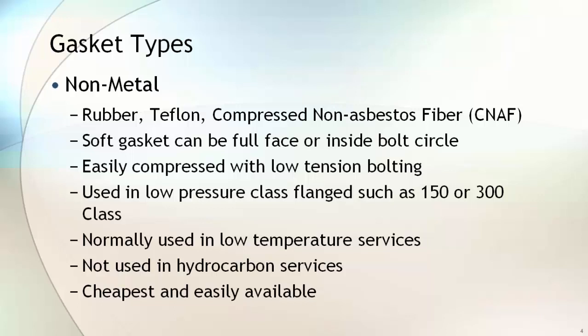Starting with non-metallic gaskets, the most common materials used are rubber, Teflon, PTFE, and compressed non-asbestos fibre. These are also known as soft gaskets. They can be full face or inside bolt circle, and can be easily compressed with low-tension bolting. This type is used in low pressure class flanges such as 150 or 300 class. They cannot be used in high temperature or hydrocarbon services. Non-metallic gaskets are the cheapest and most easily available.